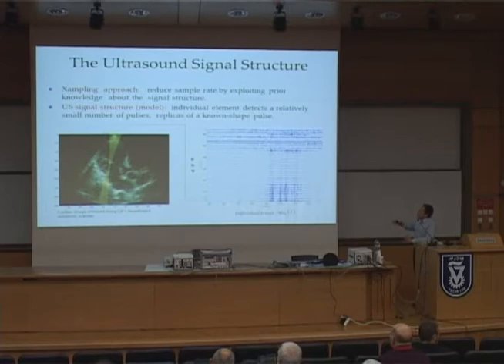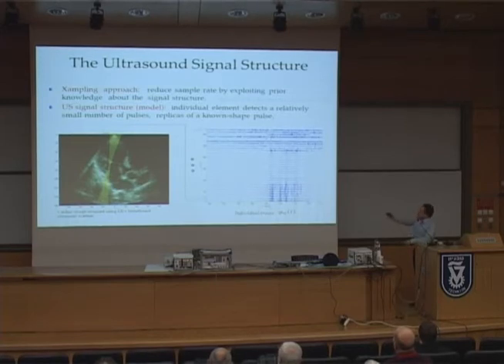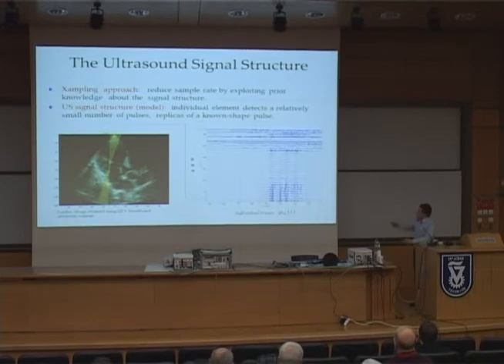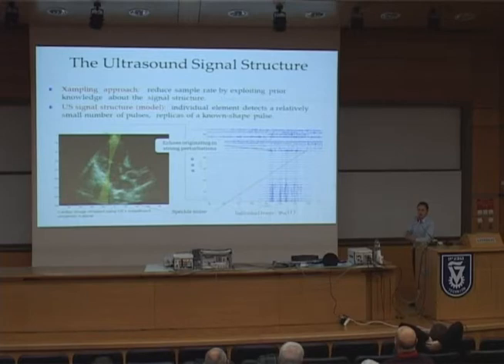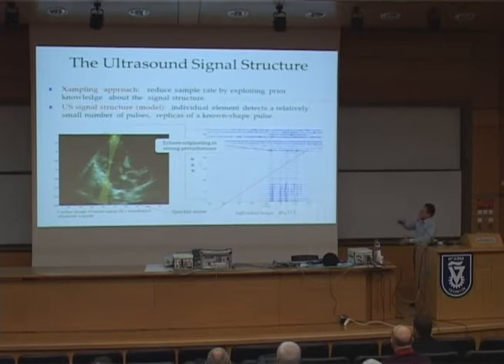The xampling approach means we can reduce the sampling rate by exploiting some knowledge about the structure of the signal. In the context of ultrasound, previous work by Tanya Chernyakova and Yonina Eldar showed that the ultrasound signal detected by each individual element can be modeled as a stream of pulses — a relatively small number of pulses corresponding to strong reflections from strong perturbations in the tissue. We also have what is known as speckle — interfering wave patterns from microscopic perturbations — but in our work we regard speckle as noise and focus on detecting the strong perturbations that give rise to strong echoes along the path of the transmitted pulse.